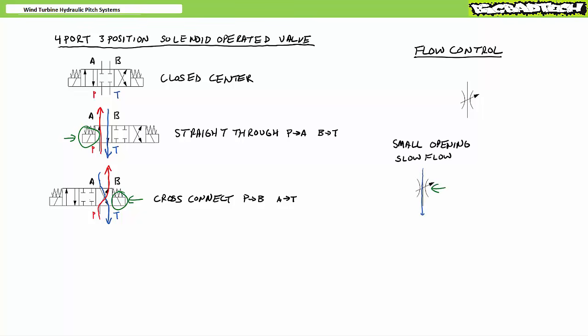As the size of the orifice in the adjustable flow control valve is decreased, less fluid is permitted to enter the hydraulic system, and actuators would extend or retract slowly. Conversely, as the size of the orifice in the adjustable flow control valve is increased, more fluid is permitted to enter the hydraulic system, thus the actuators would extend or retract quickly. In summary, by varying the size of the orifice, one directly influences flow rate, thus directly controlling the speed of the actuators. Now combine these two aspects, directional control and flow control.